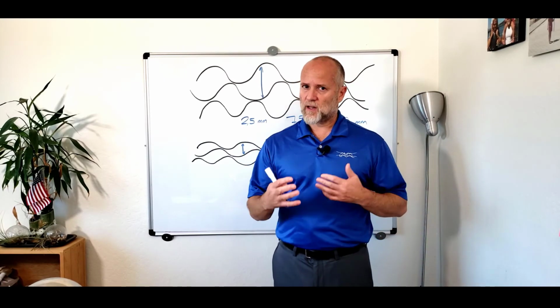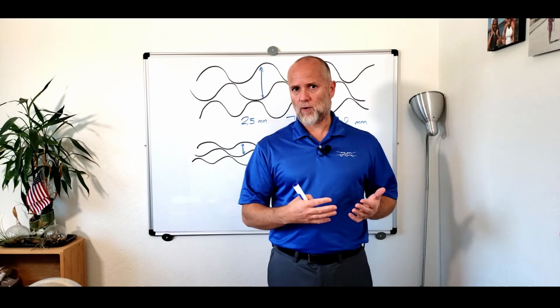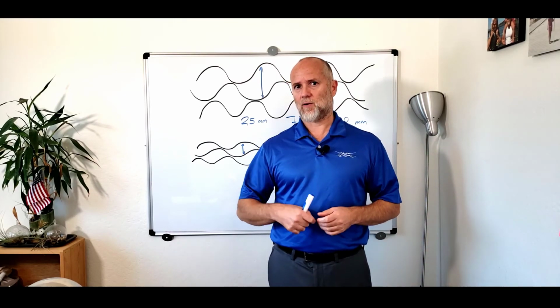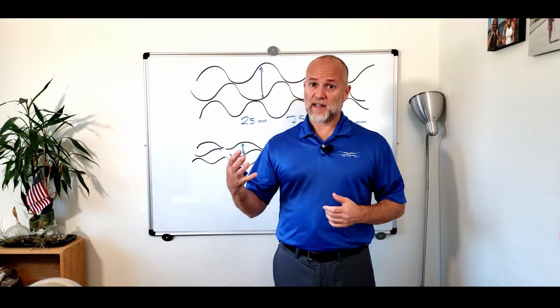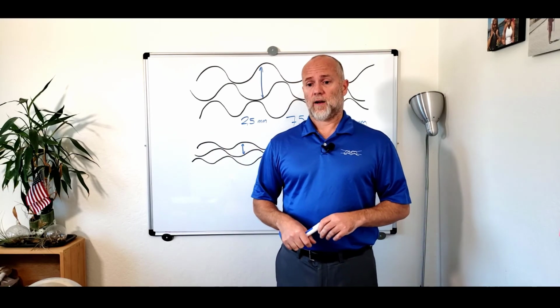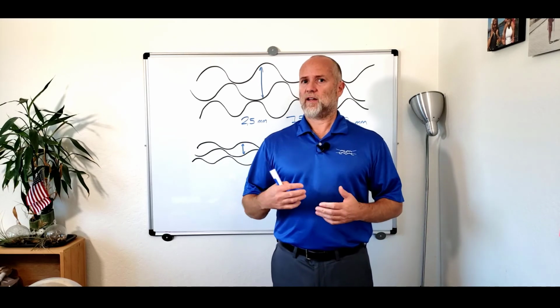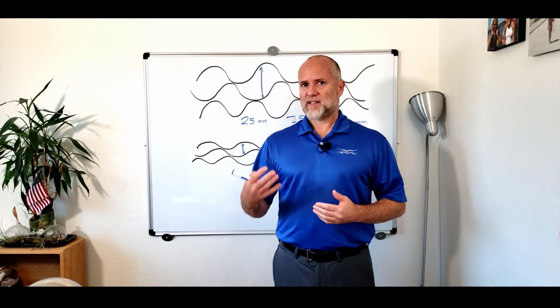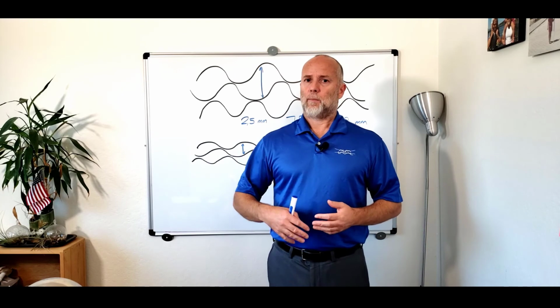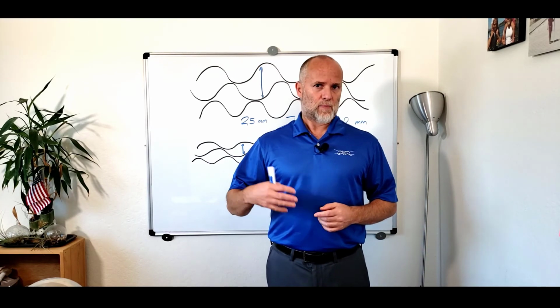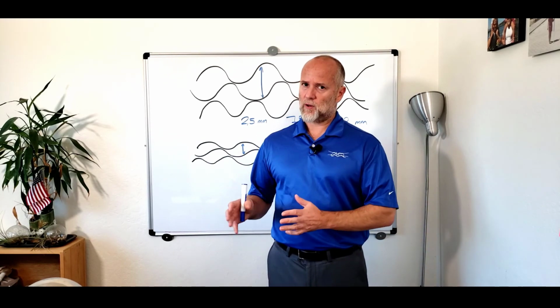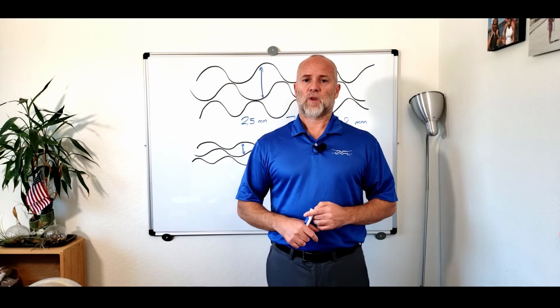With this kind of filters, of course, you screen out fairly large particles. They are not particularly helpful for another kind of fouling, which is very fine particles, dust, sand, seeds from the cooling tower, and scaling from the water, depending on the quality of the water. At that point, the shear stress inside of the heat exchanger is more important, but we have discussed this concept at length in previous videos, so we will not talk about that in this video.